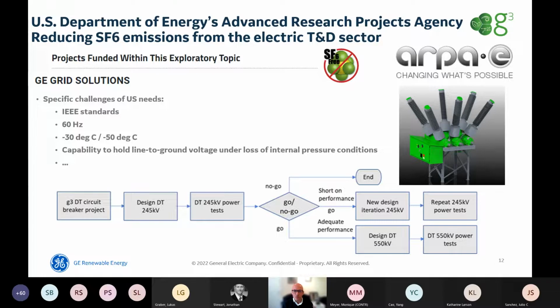So based on all that, we're designing now and starting to design, thanks to that funding opportunity, a 245 kV interrupter. If we're lucky and that interrupter is quickly successful, then we can basically use it twice to make a 500 kV dead tank breaker.